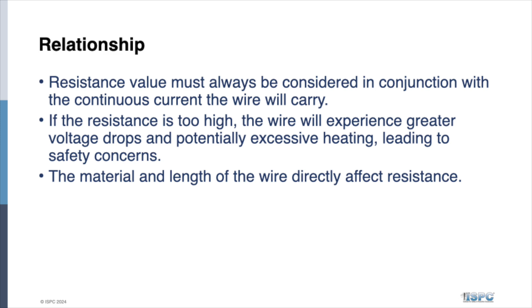If the resistance is too high, the wire experiences greater voltage drops, okay? We've already said the material and the length of the wire directly affects the resistance. And then here's a kind of a breakdown. This is a standard 2-aught temporary ground, 15 foot long, probably one of the most standard grounds that's on almost every line truck in our industry, right?